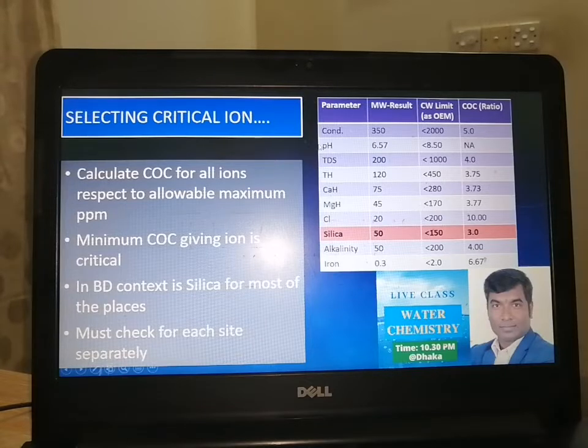Once I have the makeup water analysis report and the OEM limits - the limits given by the OEM - I have to calculate the cycle of concentration for every individual ion, such as conductivity, pH, TDS - all the results from the makeup water analysis.